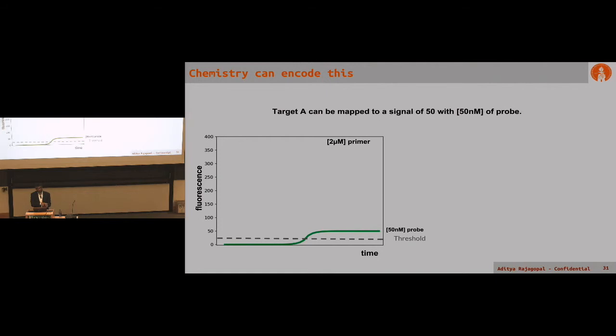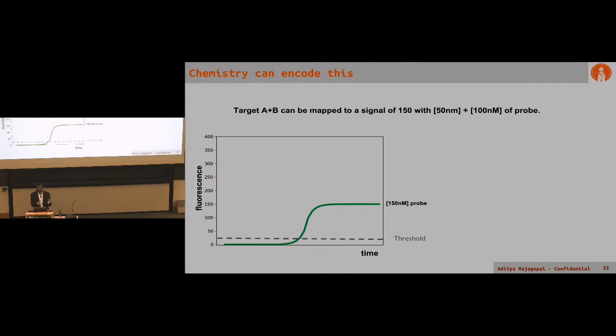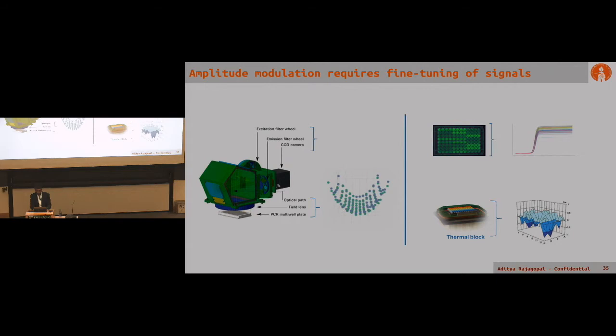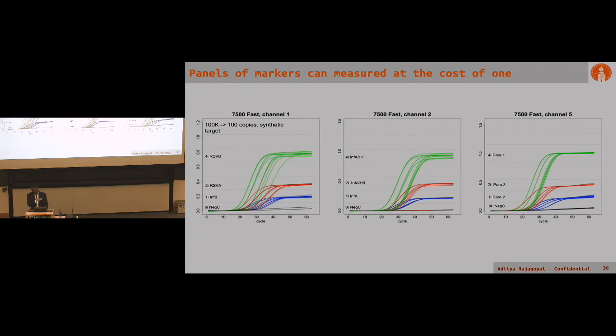What this lets us do is take a set of PCR reagents for measuring cancer markers like BRCA1, and engineer a cocktail to have a very deterministic signature. You can map any unique combination of targets to a unique fluorescent signature. But amplitude modulation does require a few other things. There's a whole bunch of signal processing you have to do to accommodate for things like thermal uniformity across the instrument.